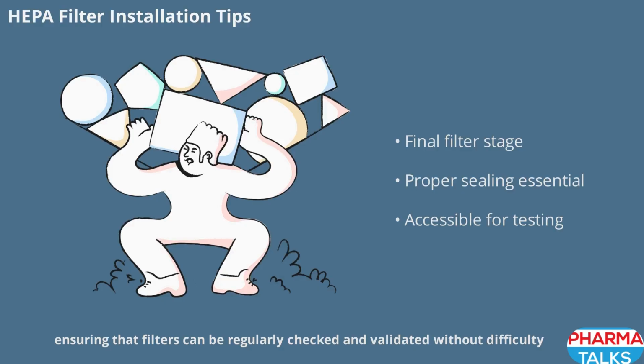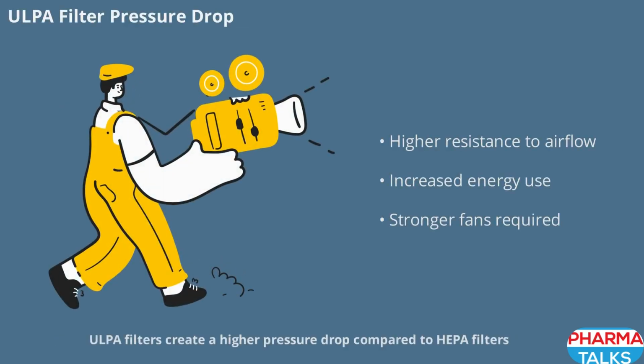validated without difficulty. ULPA filters create a higher pressure drop compared to HEPA filters, which means they resist airflow more and require stronger fans to maintain the same air volume. This increased resistance leads to higher energy consumption and impacts HVAC system design. When considering ULPA filters, it's important to account for these factors in both initial installation and ongoing operational costs.